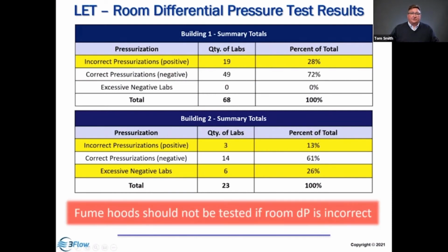So this shows the results of pressure measurements on the lab spaces in two buildings. It was designed to be under negative pressure. We expect it to be under negative pressure for safety. We go in, and we find 30% of the spaces in this building are out of pressurization. So that immediately says to us that it's not properly balanced. The secondary containment of the space is being jeopardized, and so we need to ensure that it's properly pressurized.